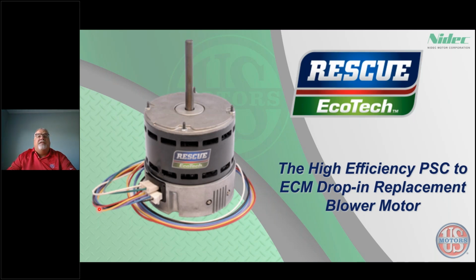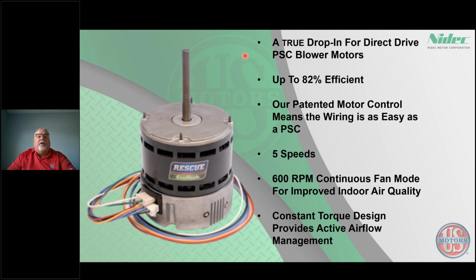The main difference is this is a true drop-in replacement for a PSC motor. So you're taking out a PSC, permanent split capacitor motor with a capacitor, and putting in an ECM product that gets up to 82% efficient. We're able to do that with a patented motor control, and it takes that high voltage signal that would normally tell the PSC motor how to run, and tells this motor how to operate.